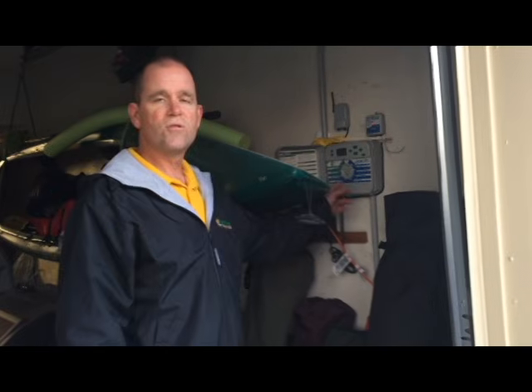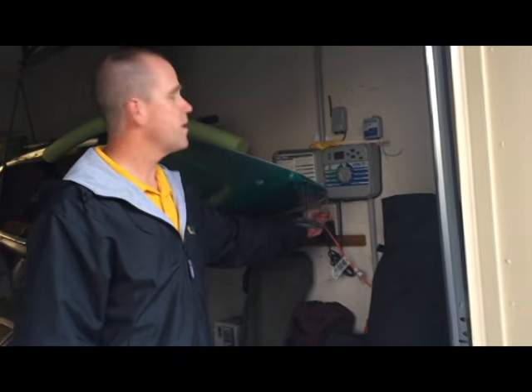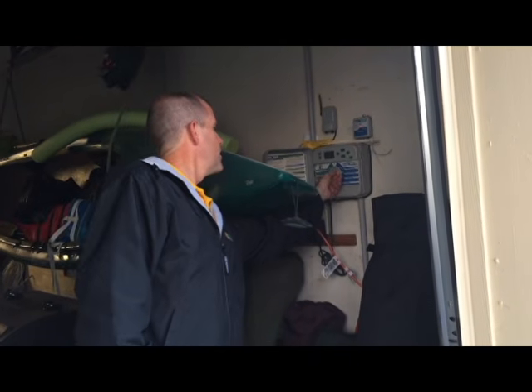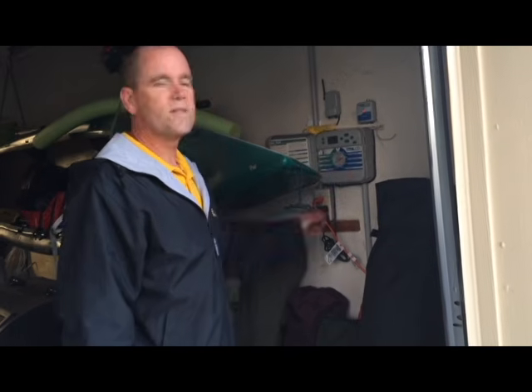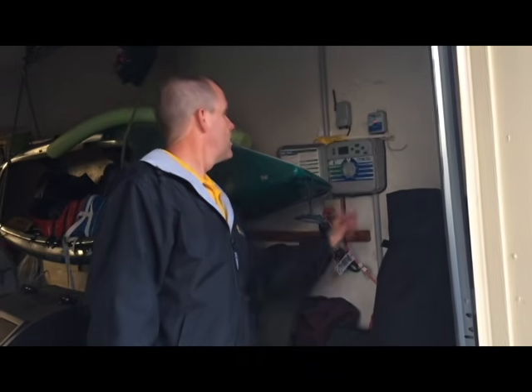At the sprinkler controller, I'll go to manual stations and run one station for a second. Since I've turned the water off, it's not actually going to come up and start running—if it does, you didn't get the water all the way off. But this opens up the valves and releases some pressure on the sprinkler system so it doesn't spray all over you when you open up the other valves. We'll just leave that on for a second.